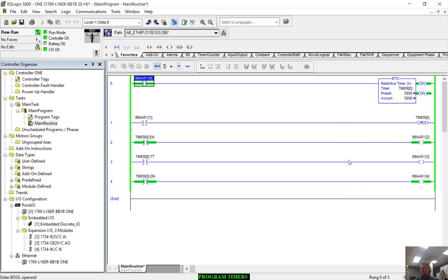So that is retentive timers. One nice thing with retentive timers is that we can do something as simple as Control T this, turn it back off again. But I can come in here and go Control T and Control T again, and that maintains that information. It retains it. It holds it at 1515, for instance, in this particular case. That's how long I held it: 1.515 seconds is how long I held that on.